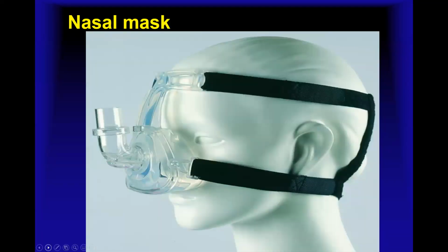Nasal mask is just one of many. This looks like an old Respironics. Again, some of these have gotten better. Nasal masks used to be the standard of care. They're not as popular anymore. It's not that they're not out there. They're just not as popular, in part because if a patient is a mouth breather, it can be really problematic. The flow goes in the nose and out the mouth. I'm not saying all of it, but sometimes it's hard to achieve the prescribed therapeutic pressure for the patient.